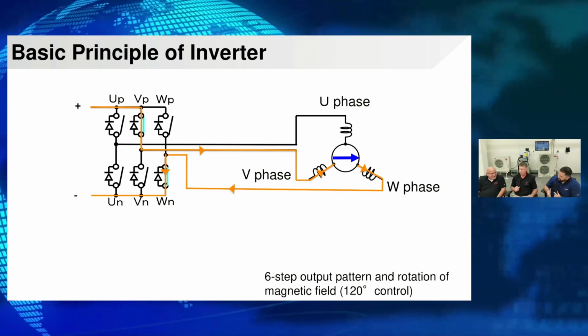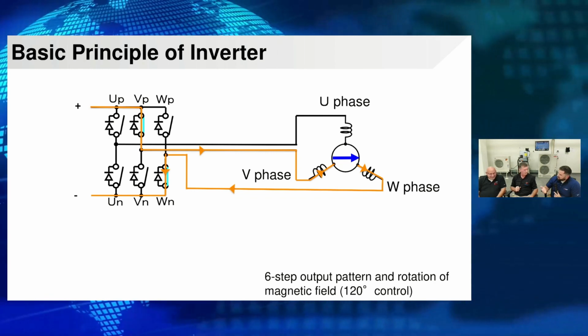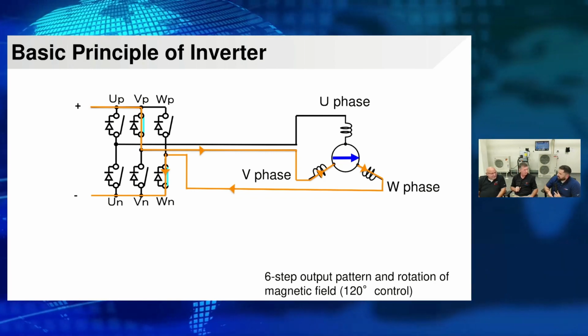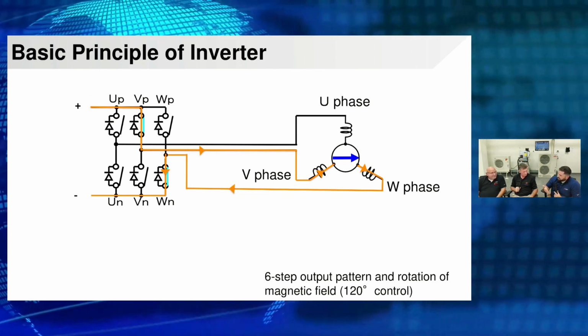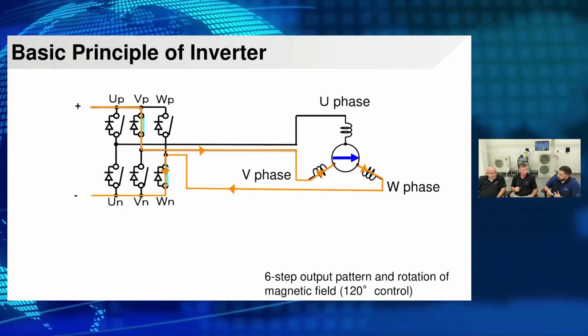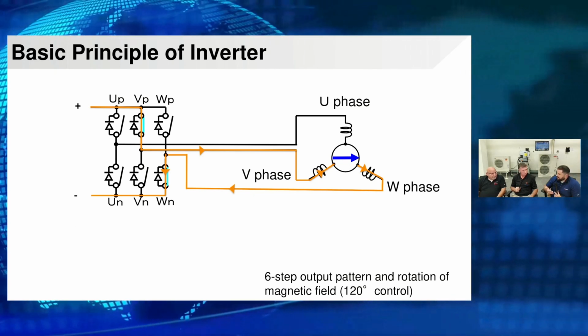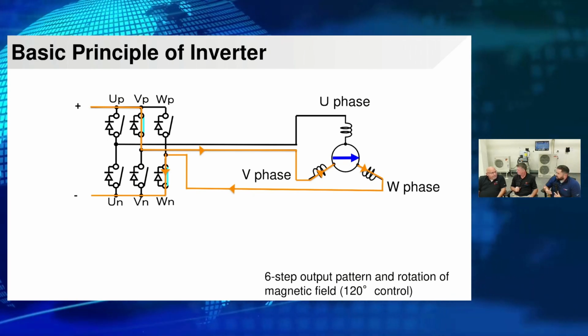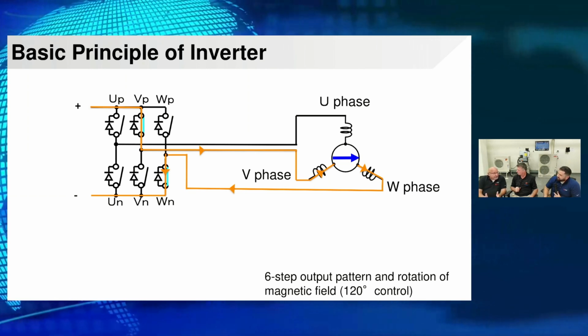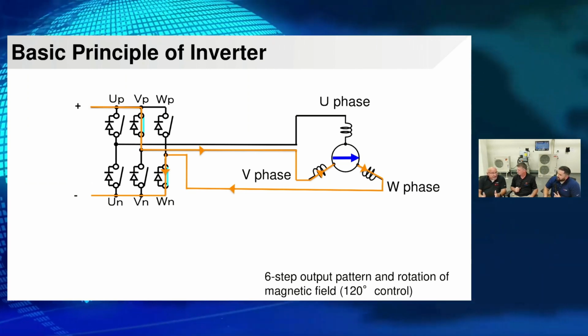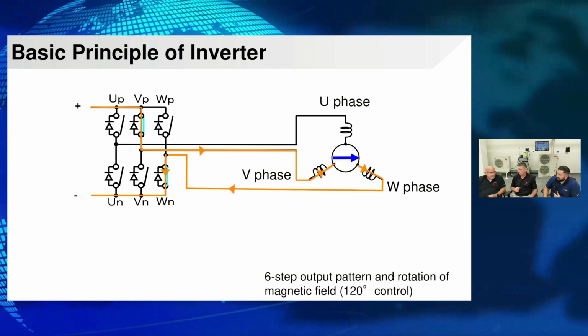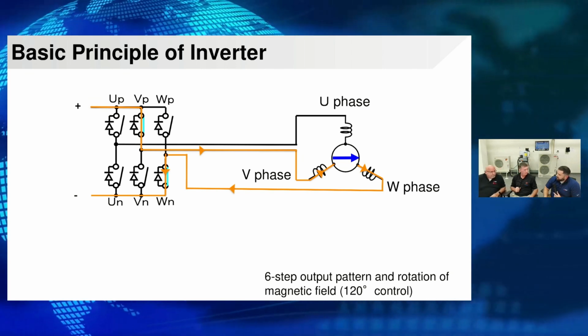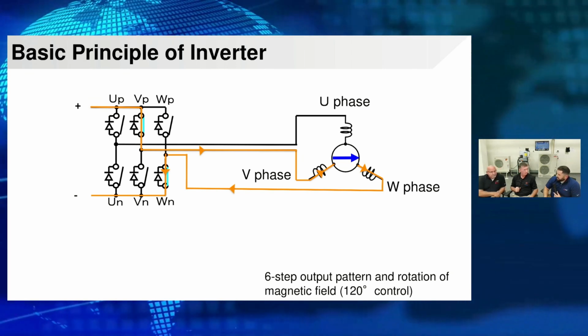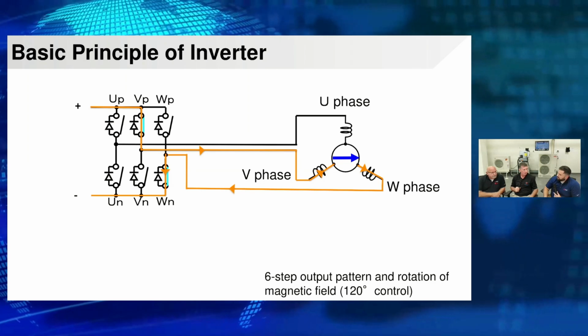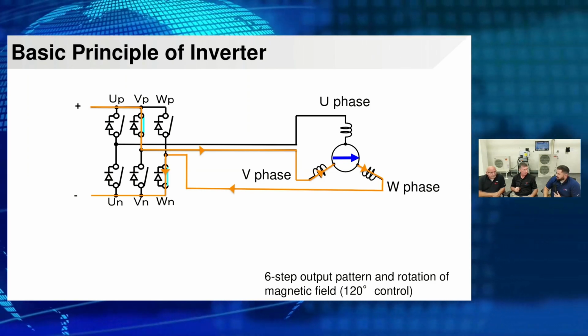We need to verify and isolate the power. We need to separate those two components. Let's test each leg of the compressor windings without them connected. Let's test the U, V, and W wires without them connected to that compressor. Make sure we're balanced, because if the resistance is balanced electrically, the windings are in good condition. Correct. So to avoid compressors being diagnosed as bad when really it's an inverter issue, it's a board. Yeah, we've got to make sure we isolate the components.